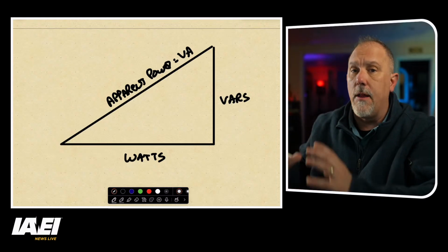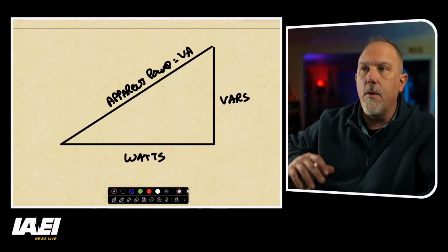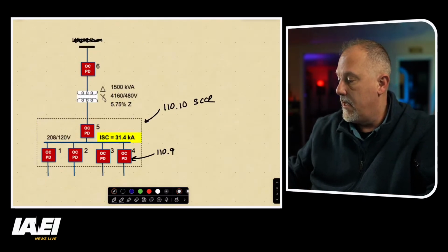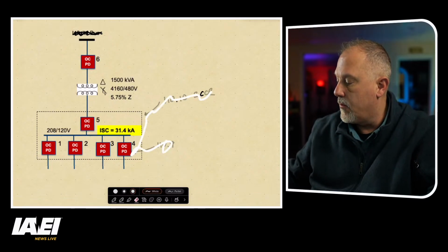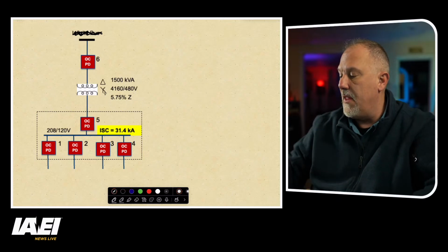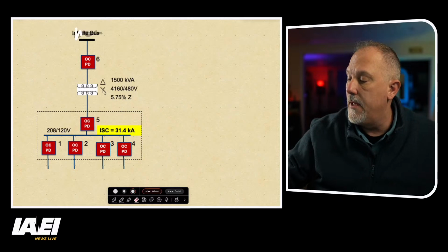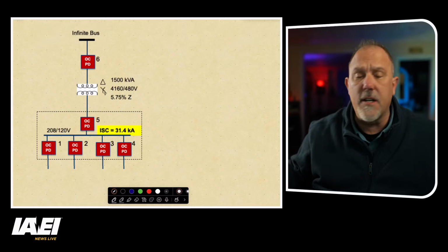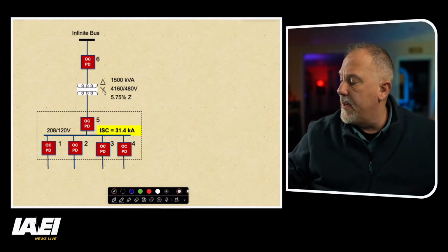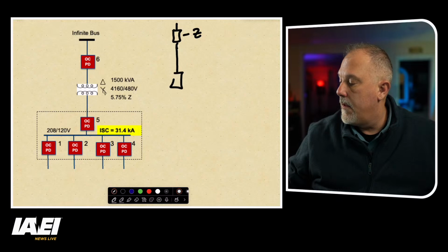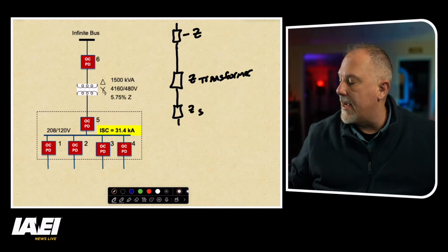So we use this triangle for a lot of things, and what we'll use it for during the fault current analysis is we're going to have to take this circuit. Let's say that I was going to assume an infinite bus. I would have to convert this into an impedance diagram. So that infinite bus would be a Z. This would be the Z for the transformer. This would be the Z for the secondary conductor. And then I'm at the bus.